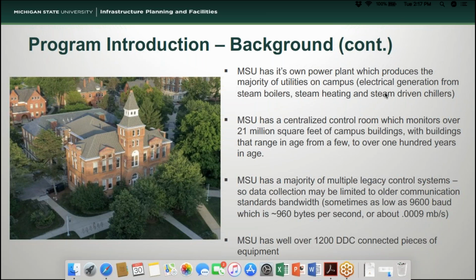We do have a centralized control room where the majority of buildings are connected and they all report back. And we have 7 operators that monitor our equipment day in and day out for alarms and other operational issues that are more emergency issues. Because of the age of our campus, we have some buildings that are just a couple years old. In fact, we have 2 buildings that are in construction right now. But we also have a number of buildings that range beyond 100 years in age. So we have quite an array of control systems on campus.